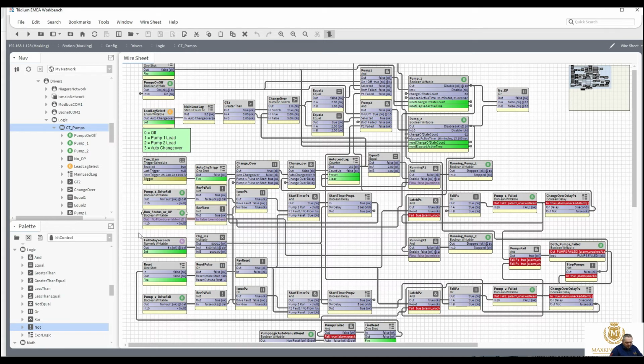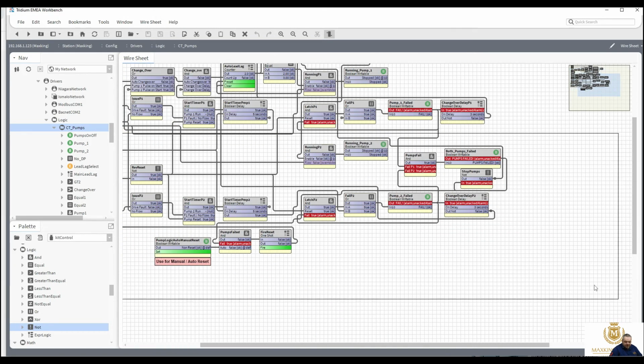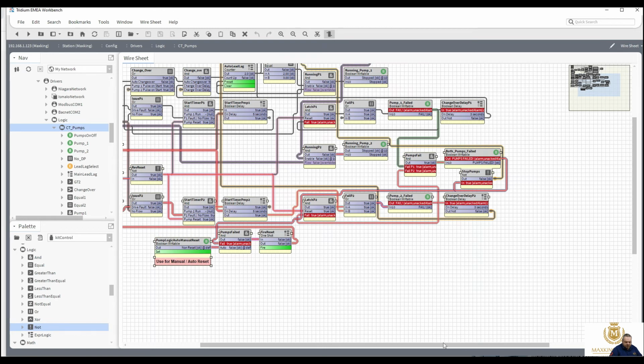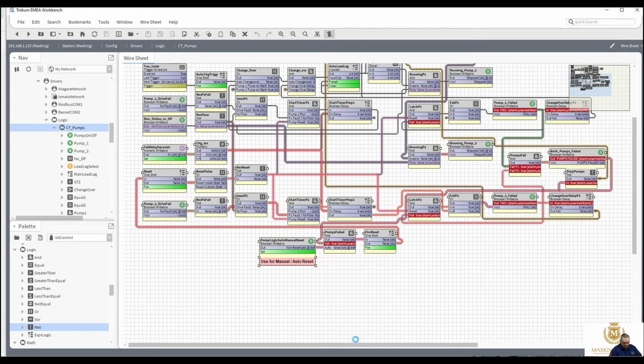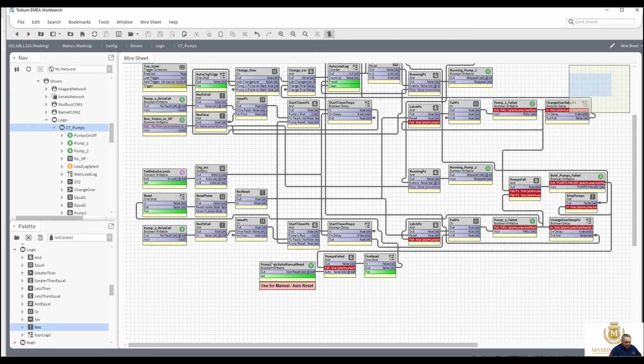So I'm going to spoil the way I've laid this out a little bit now, but I do want the option to not have a DP in the logic, i.e. if we've got a situation where we haven't got a differential pressure switch or we haven't got a flow switch, and I want the option to put something in there to stop that.